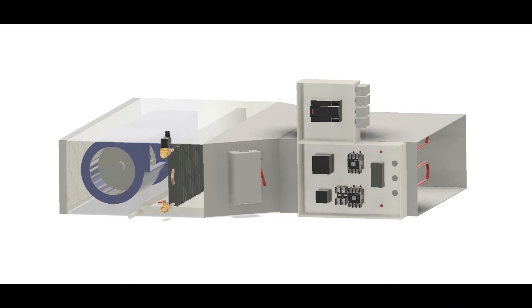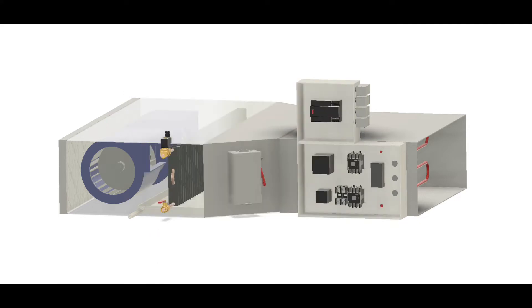Once you have power to your fan coil unit, if it's in heating mode and it's not heating, some common things to check for that I've noticed that will be wrong or incorrect that I've found. Make sure your BAS is set to heating mode. Check the temperature set points. Check the room thermostat if you just have it controlled by a remote thermostat. Make sure it's in heating mode.